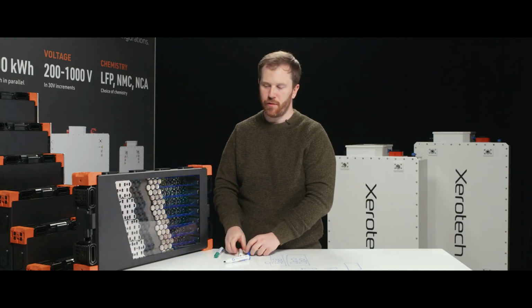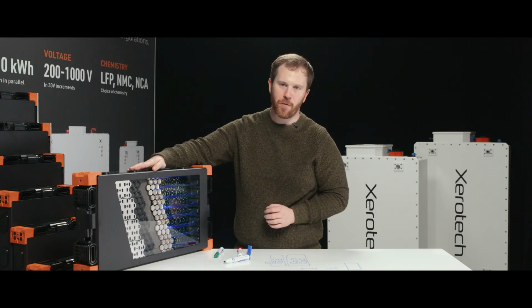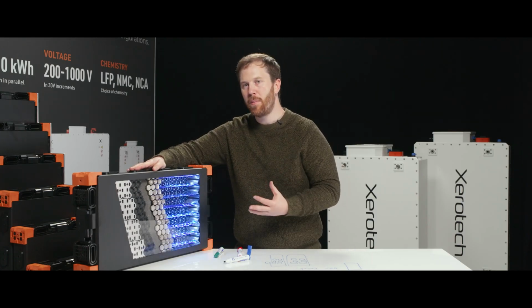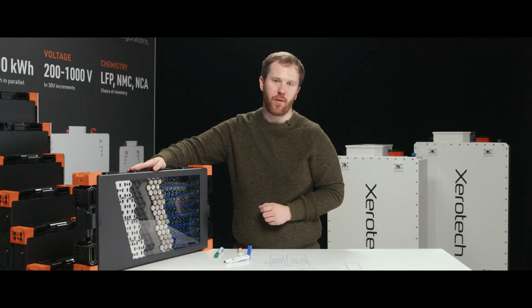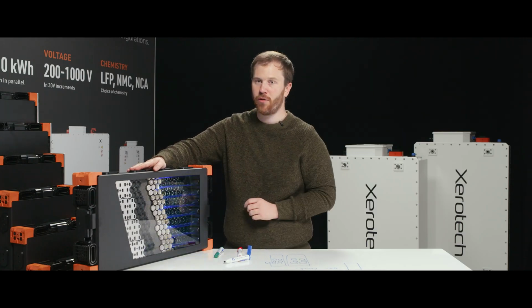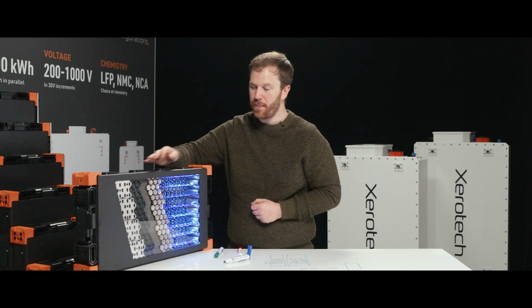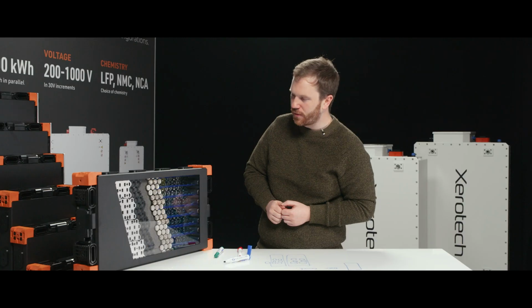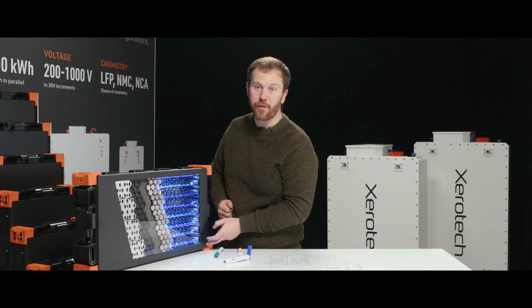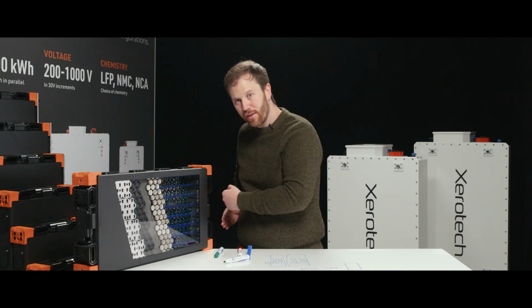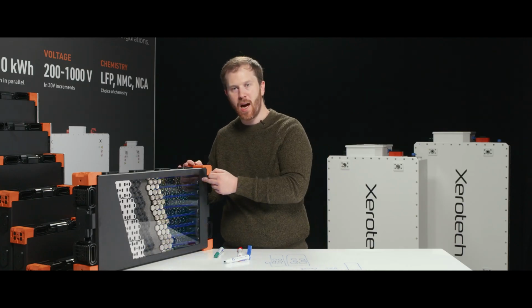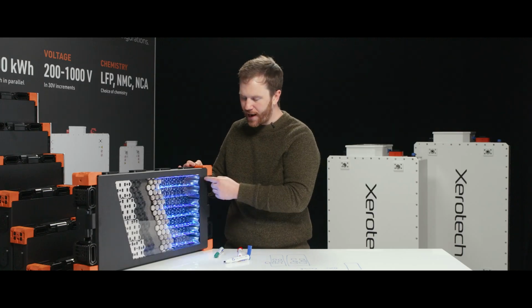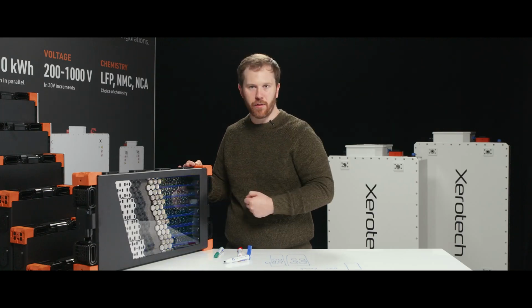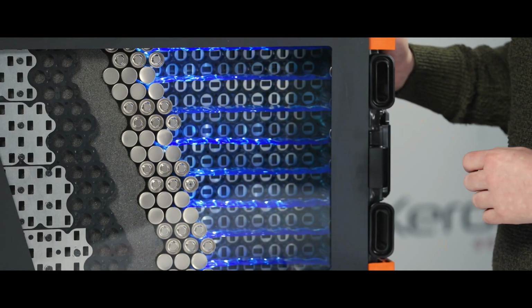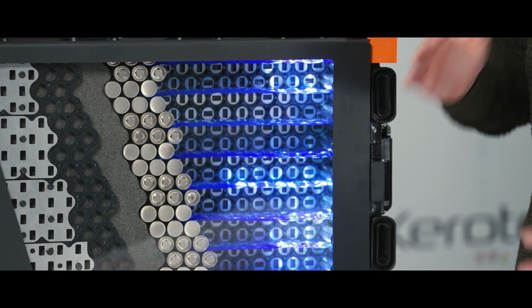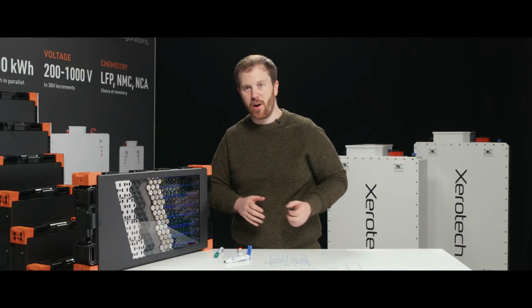From a temperature perspective, it's obviously impractical to measure every cell in the pack. So typically you measure a couple of different sensors at a couple of different points. Some manufacturers might only use 1 or 2 sensors per module, or maybe even 1, depending on. So in a Xerotech module, just because it's in front of us here, we measure 4 points on one side of the module. That's on the coolant exit side of the module. So basically it will be the hottest or the coldest point on the module. The last cell at the end of the module on the exit is where we measure. There's different control strategies depending on what you are trying to achieve. Some differences between the two, but in general, all are acceptable.